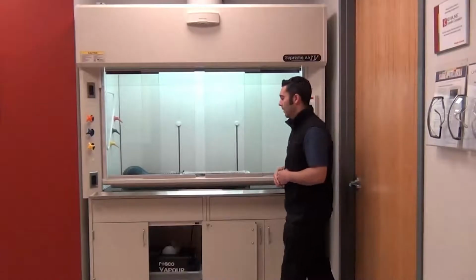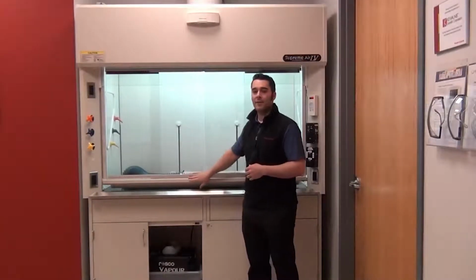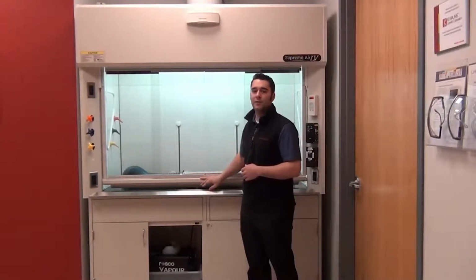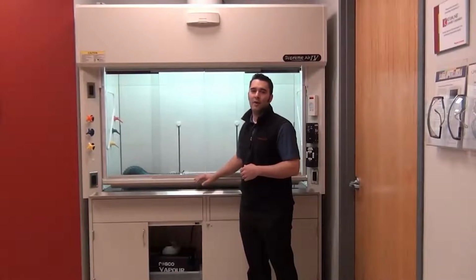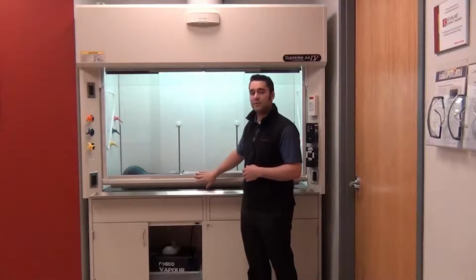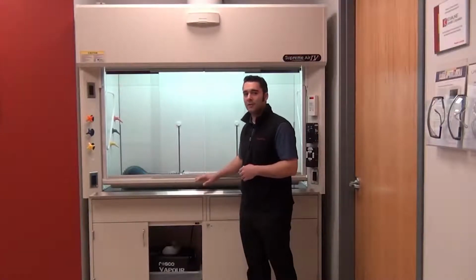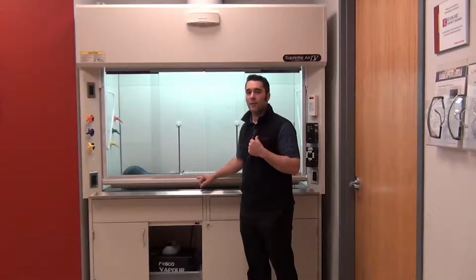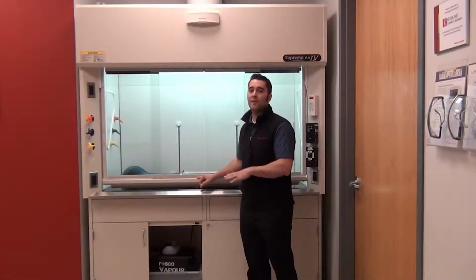So even though we have safety and savings built into these fume hoods, the safety is always paramount. And because this just came out of shutoff mode and I closed the sash, it's not going to go back into shutoff or hibernation mode unless I reinitiate it on the fume hood display. So I'm always guaranteeing the safety of the people that are using the fume hood.